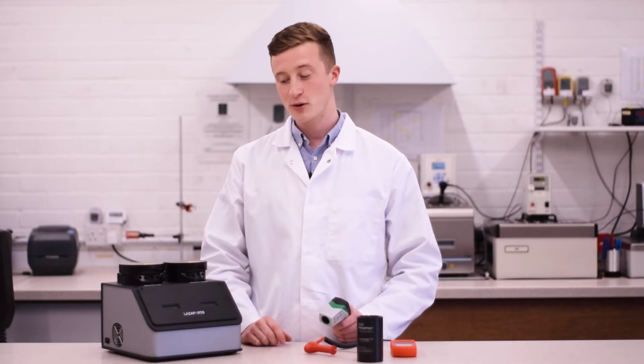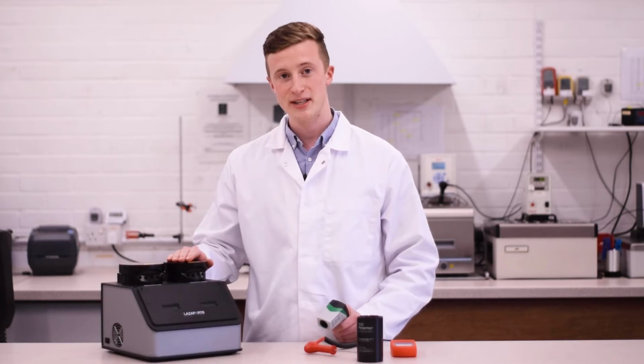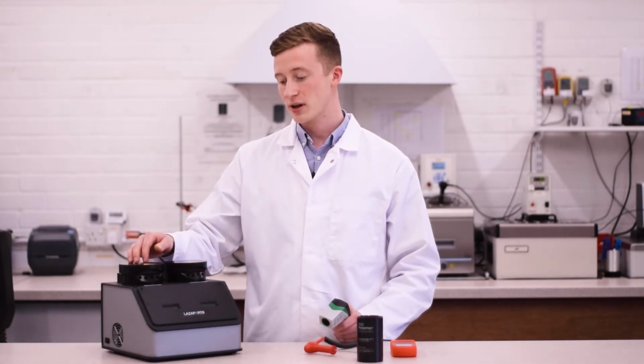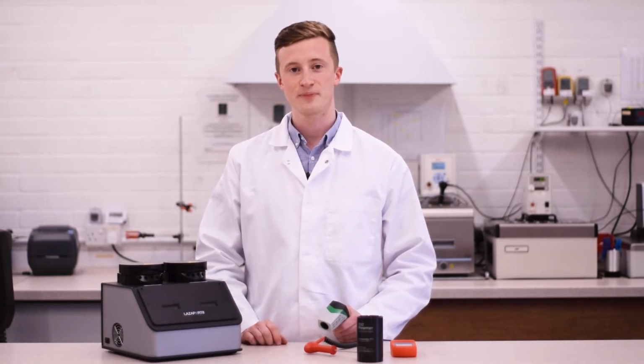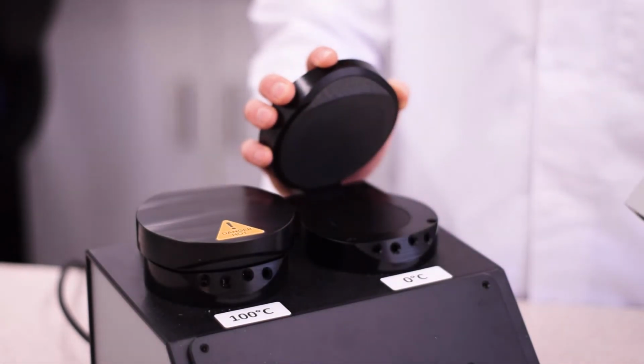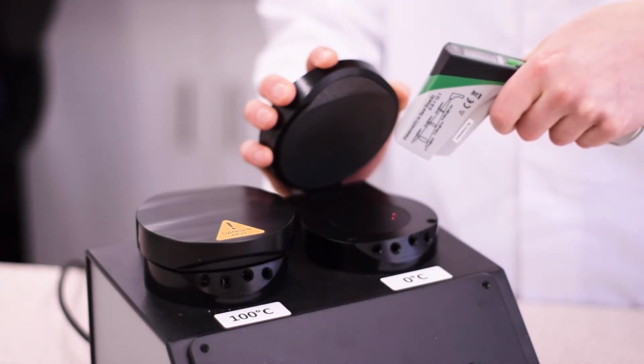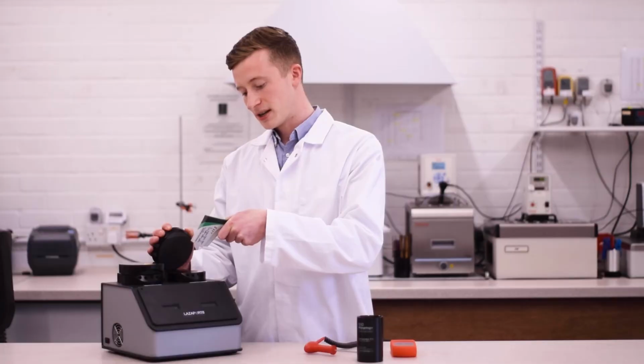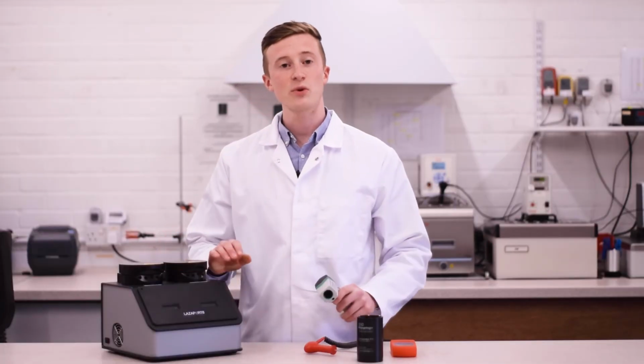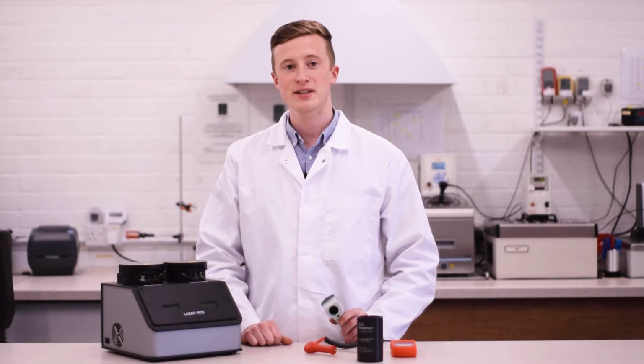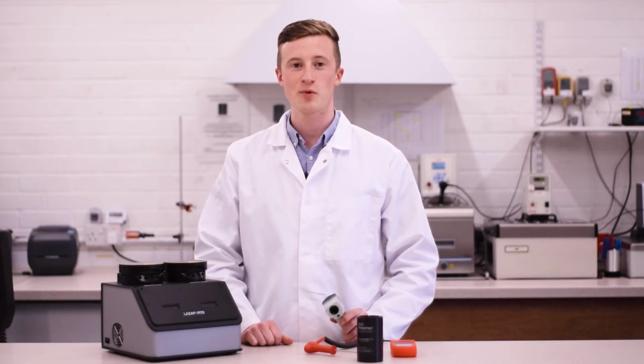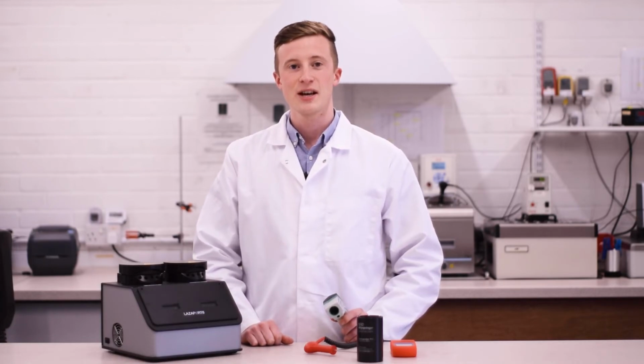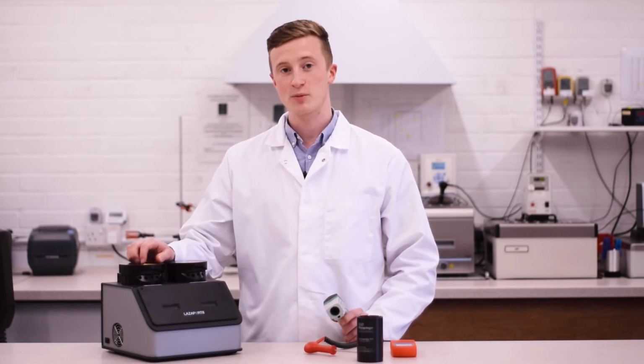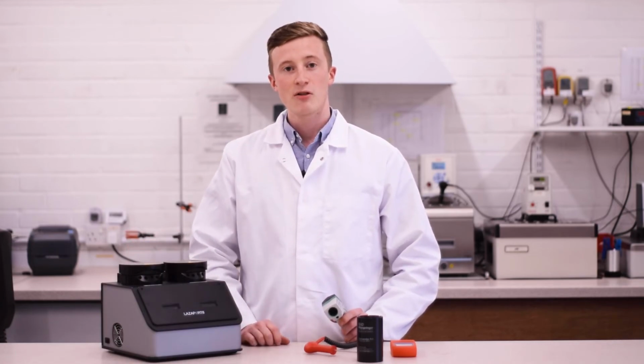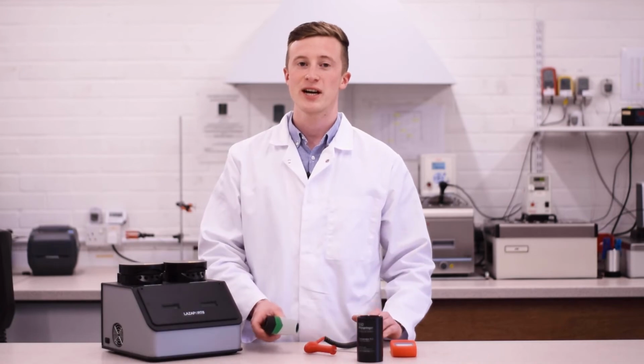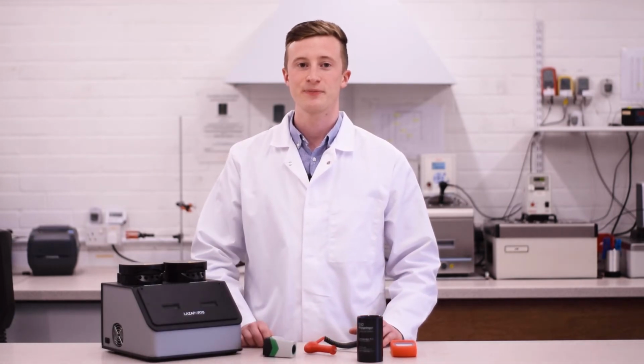One block is at a low temperature, such as 0 or -18 degrees Celsius. The other block is at 100 degrees Celsius. Simply point your infrared thermometer at the top of the block and gain a stabilised reading. Again, we recommend taking 3 temperature readings to ensure you get a consistent, reliable and repeatable reading. Repeat this process on the other temperature block also. Remember to record the temperatures on your calibration log in the usual manner.